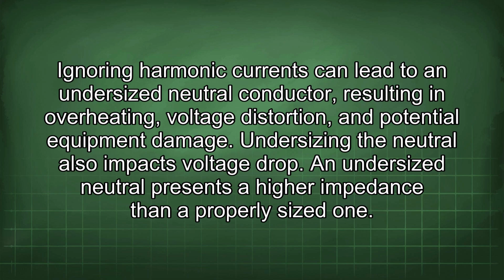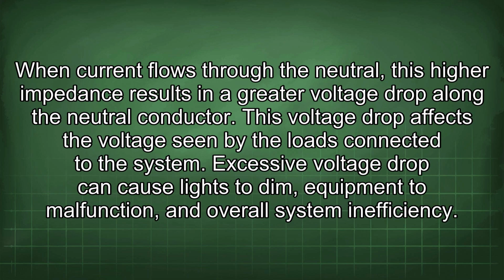Undersizing the neutral also impacts voltage drop. An undersized neutral presents a higher impedance than a properly sized one. When current flows through the neutral, this higher impedance results in a greater voltage drop along the neutral conductor. This voltage drop affects the voltage seen by the loads connected to the system. Excessive voltage drop can cause lights to dim, equipment to malfunction, and overall system inefficiency.